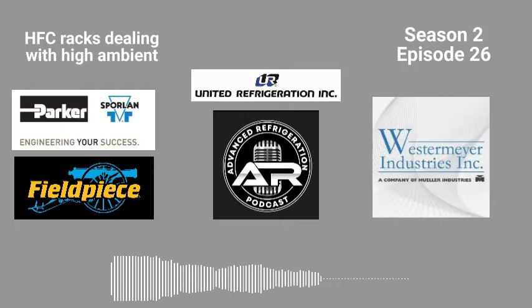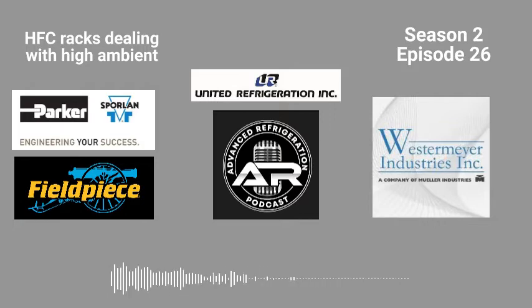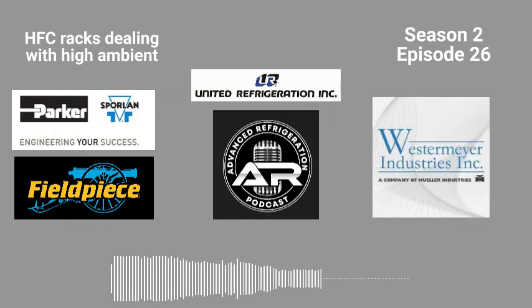Okay. Non-condensables. There's no such thing. So, yeah, guys, especially on these racks where there's been questionable stuff done, do a non-condensable test. What you want to do is shut the rack down. I generally just shut everything down. I don't pump it down. I just shut it down, force the fans on for half an hour, and check your saturation temperature. With a non-glided refrigerant, I want to see within a degree. Brett, you agree with that?